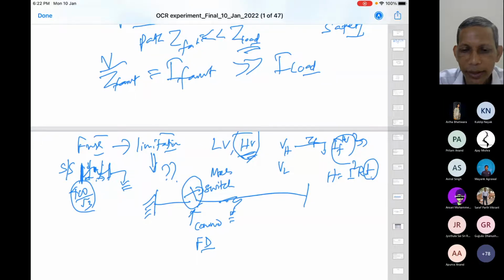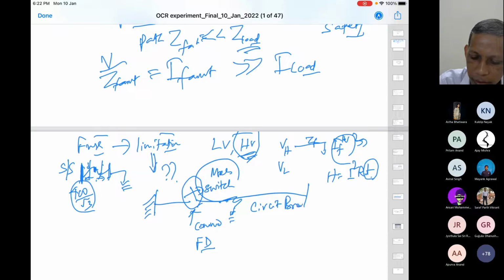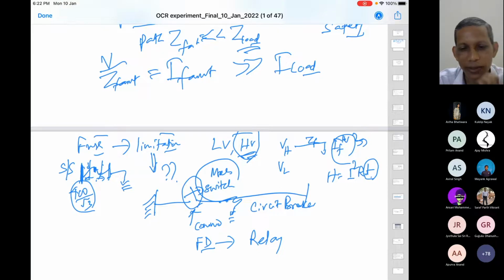In power system terminology, we call this switch a circuit breaker, which breaks the circuit, and the detector is nothing but the relay. The relay senses from current and voltage that the situation is not good, a fault situation, and then commands the circuit breaker to open. The circuit breaker of its own cannot do anything. It has to follow the instruction from the relay. That is the general philosophy.